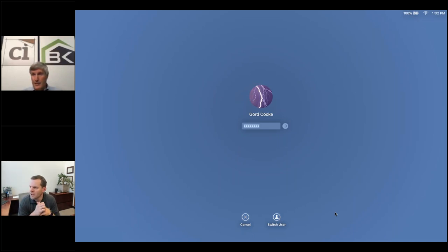One of our integrators on the call is asking if we want to go to 1.5 ACH50, can we still guarantee that it's going to perform at 1.5 when it's operated, as opposed to the enclosure test? That's a great question. You're going to have to judge for yourself a little bit. I will say this. Every bathroom fan leaks at the rate of about 12 CFM. We've actually done this measurement, 12 to 20 CFM, depending on the bathroom fan. Some are better, some are worse. As a little example, Broan has just come out with a bathroom fan that has a much tighter damper and much tighter seals because they've understood this issue. But you can imagine in a really tight house, if I had four bathroom fans, each leaking at 15 CFM, that's an extra 60 CFM. That's going to skew your results.